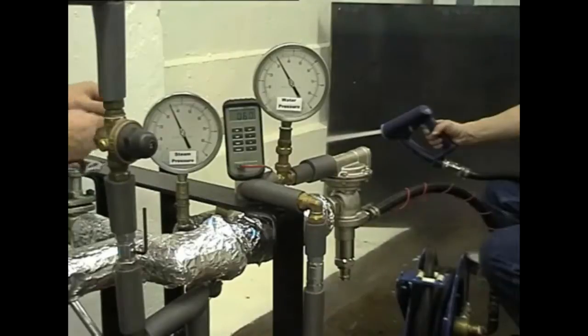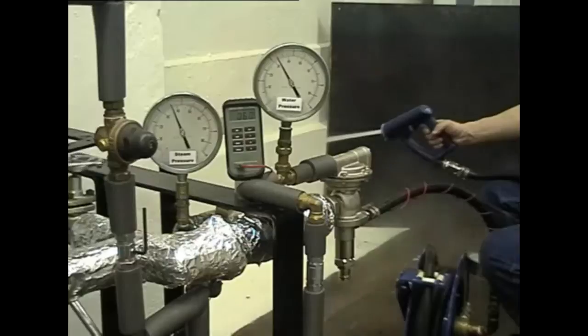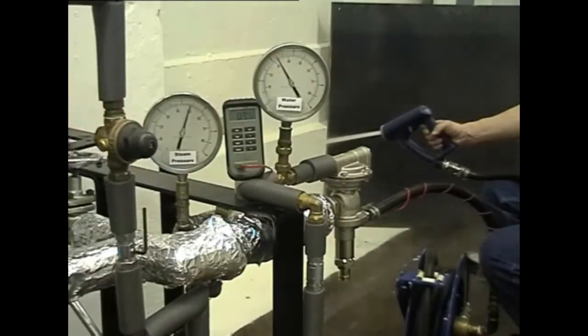Now let's see how the SWM1 reacts under a large increase in steam pressure. Bypassing the steam supply pressure reducing valve allows the steam pressure to be increased to 80 psi.